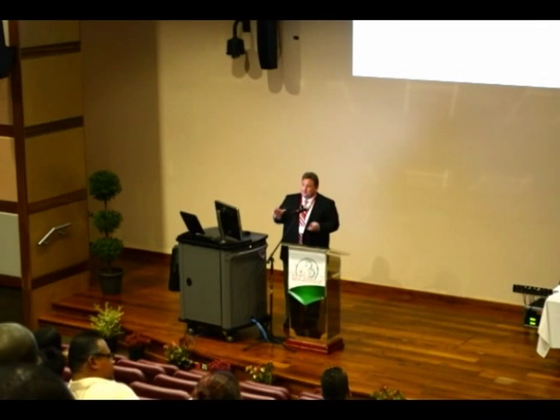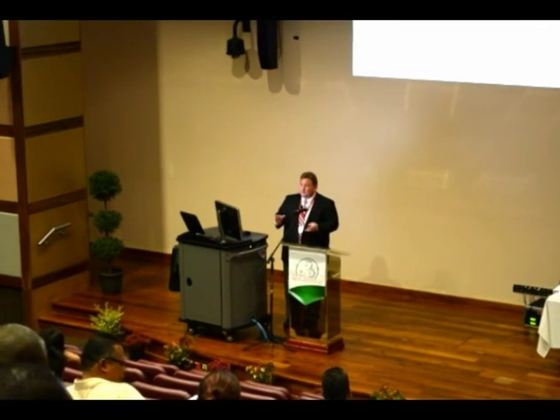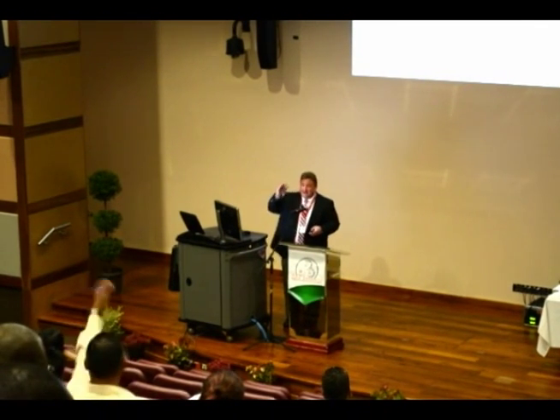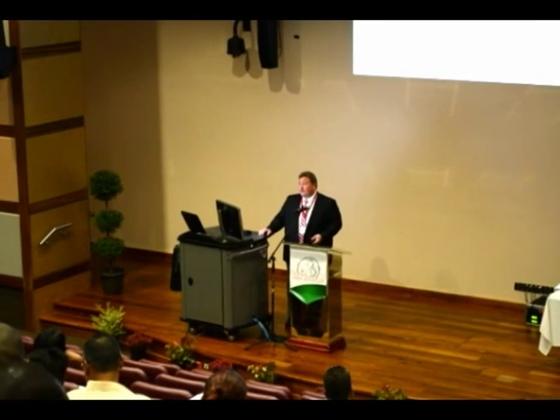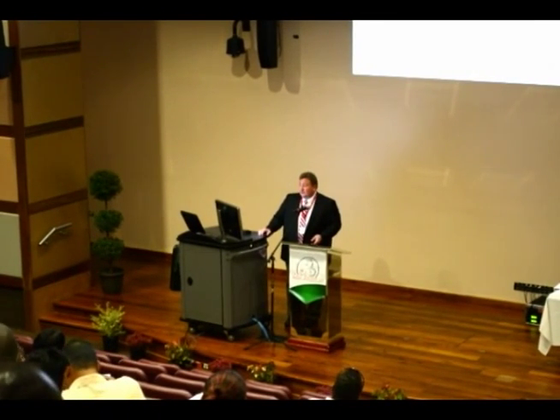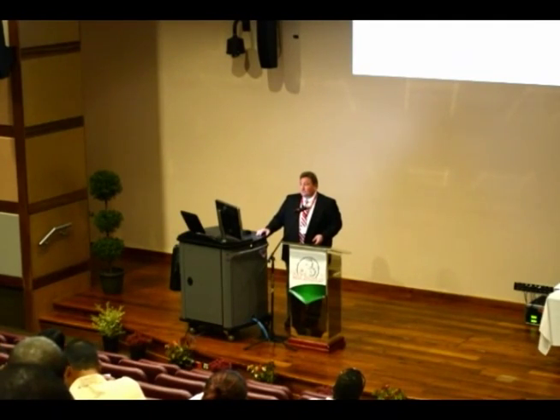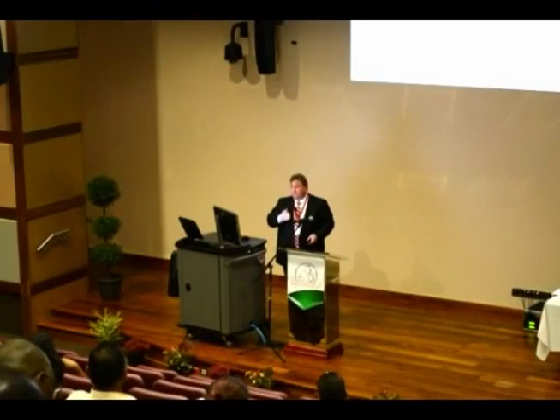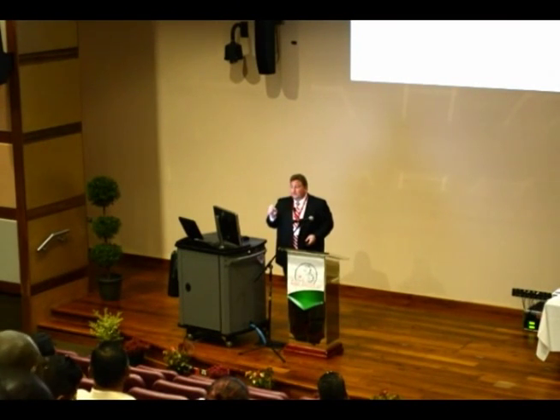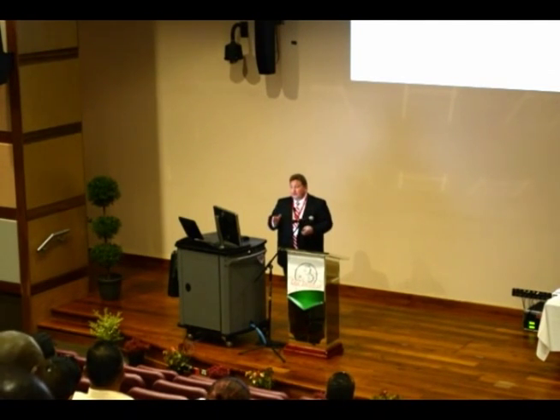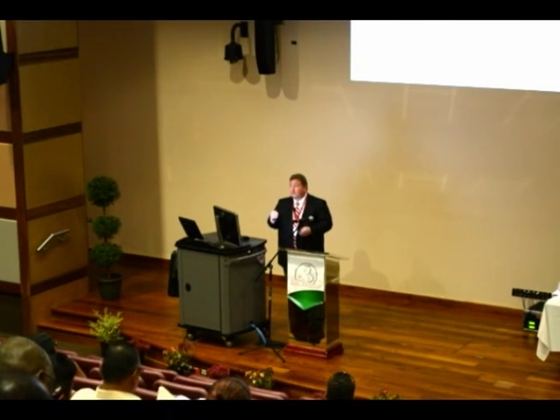Maybe you discover that the hood's not in an optimum location, or perhaps the stack has a cap on it, and you say, well, what do we do now? The point of this next session is really to talk about how do you proceed from here — how do you move forward in a systematic fashion that doesn't create all kinds of alarm, but gives you an opportunity to determine what is the risk, and then what are the appropriate next steps to solve the problem, if there is one.